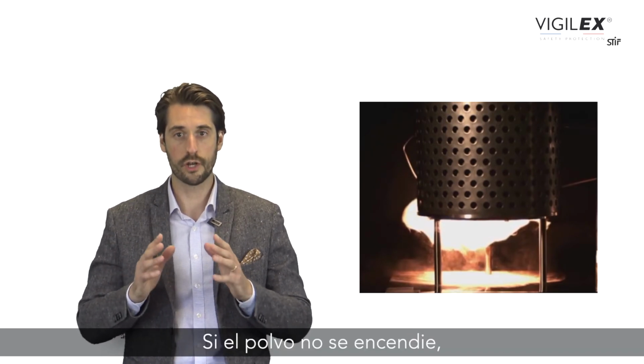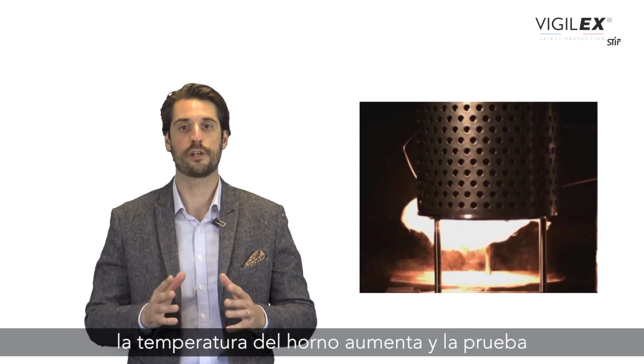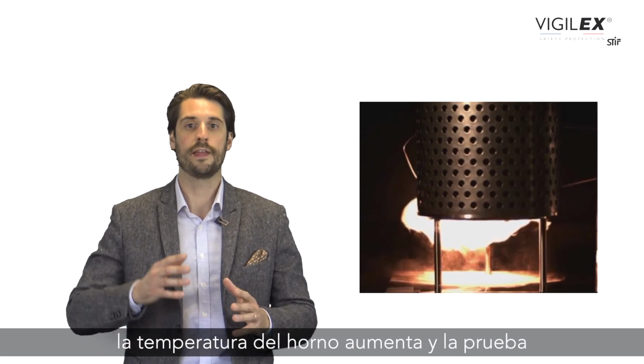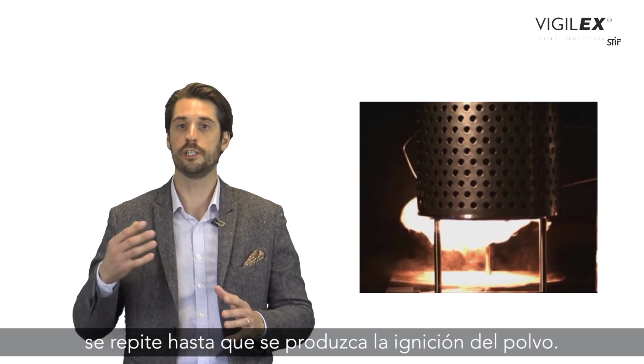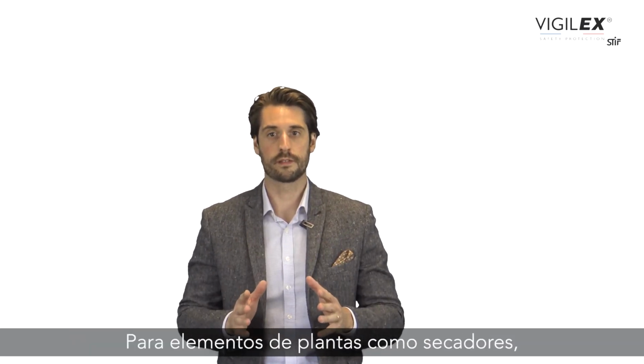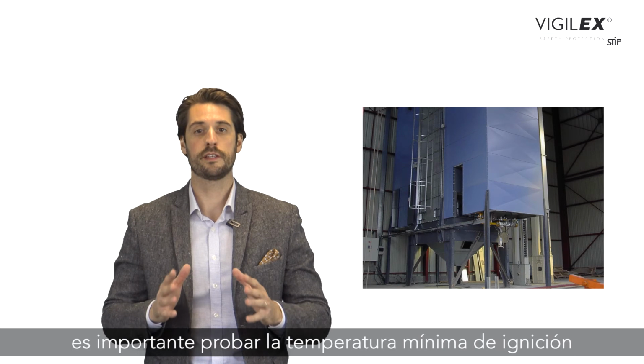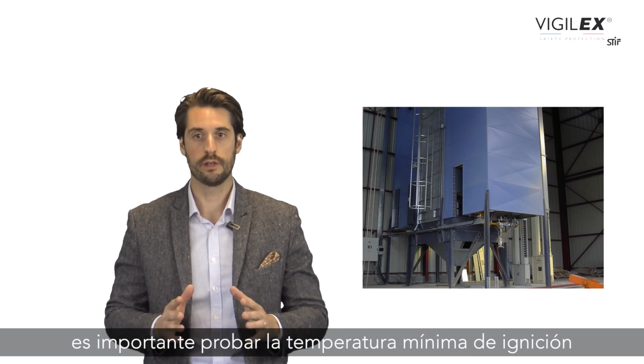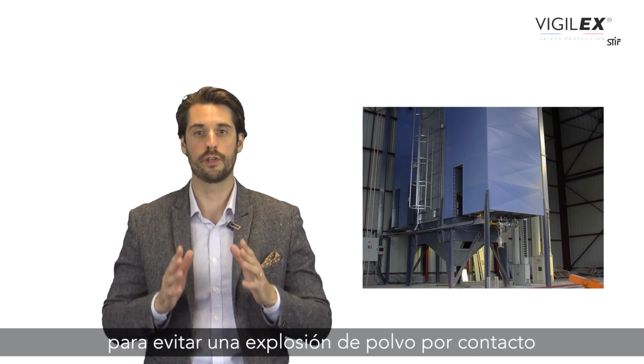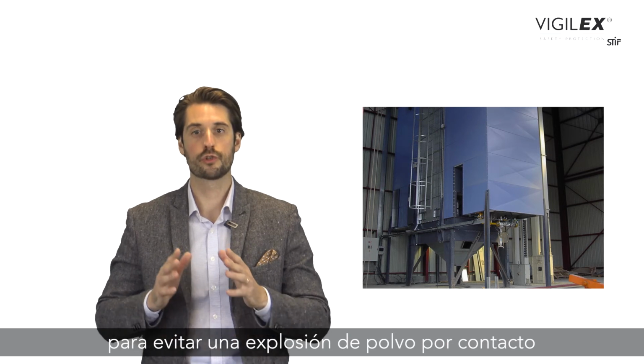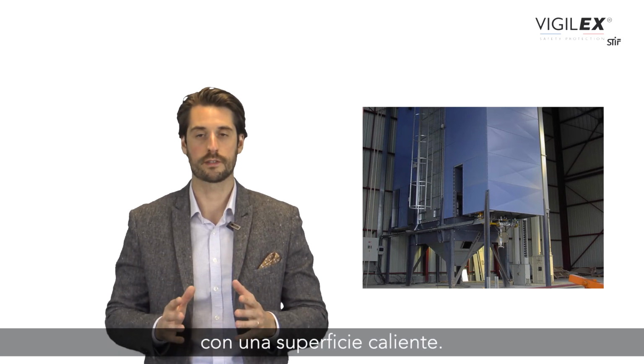If the dust does not ignite, the furnace temperature is increased and the test repeated until ignition of the dust occurs. For items of plant, such as dryers, testing the minimum ignition temperature is important to prevent a dust explosion occurring through contact with a hot surface.